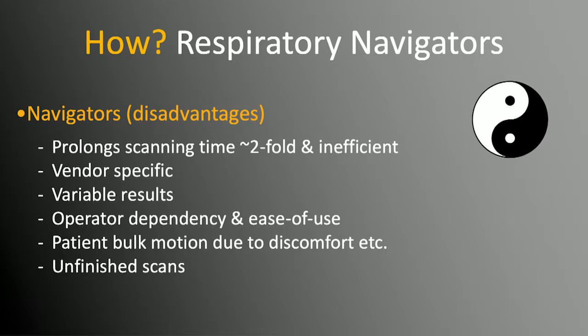However, the scan time is not only lengthy with this technology, it's also highly unpredictable because it depends on the respiratory pattern of the patient. These navigators are implemented in a vendor-specific fashion, which, however, becomes easier and easier to use. The results might be variable, and clearly there is operator dependency on how to position these navigators. This is actually a rather difficult task to do. And they cannot easily account for patient bulk motion, for instance.